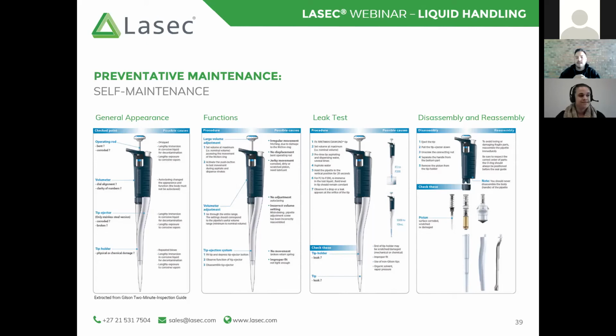The second function that we're testing is that piston again. Is that piston working correctly? Is it able to maintain and hold that vacuum inside of the pipette? So essentially what a leak test is going to show is either the liquid's going to be retained in that tip with no leaking, or you're going to have droplets forming slowly. If it's not too much damage, it might be a slow drip formation. If there is significant damage inside the pipette, it will actually just start running out. It won't be a slight drip.